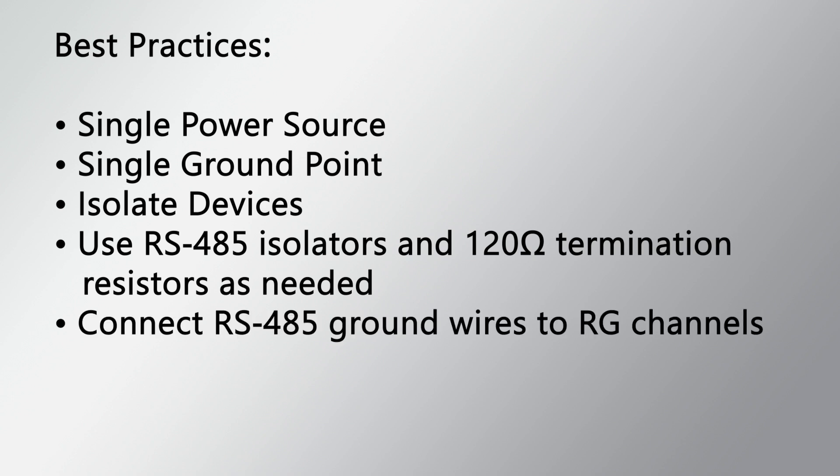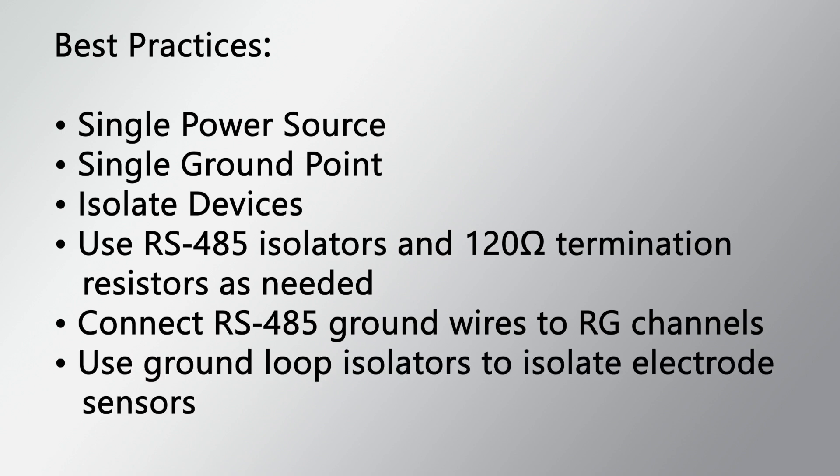Connect RS-485 ground wires to RG channels. Use ground loop isolators, such as blocking capacitors, to isolate electrode sensors. Use twisted pair wiring to reduce electromagnetic interference.